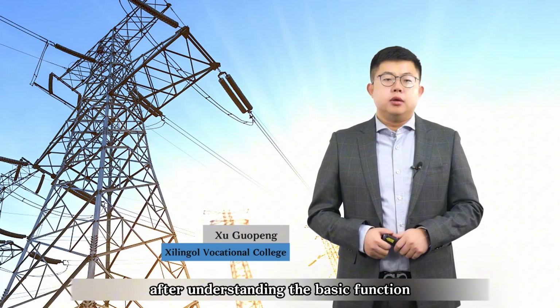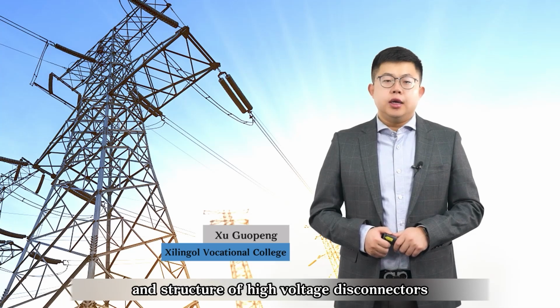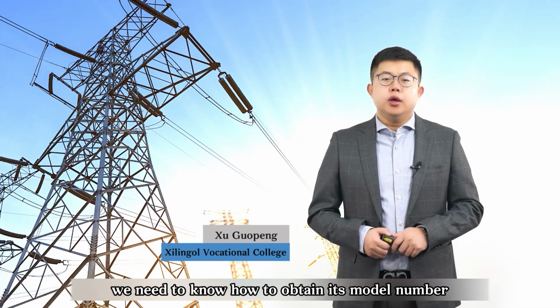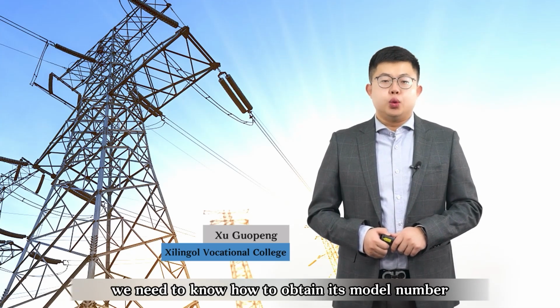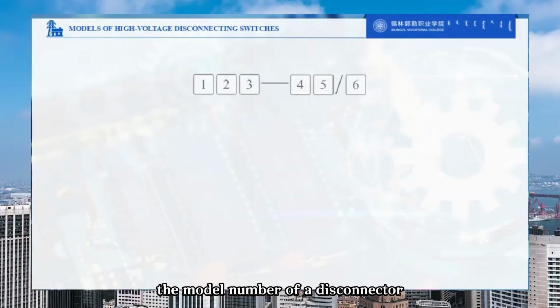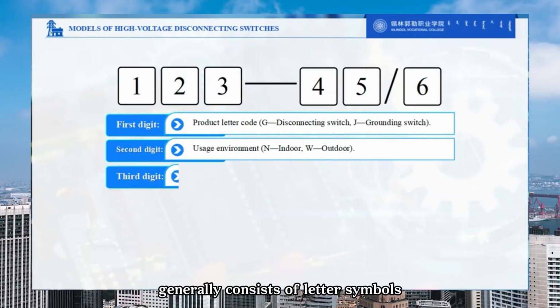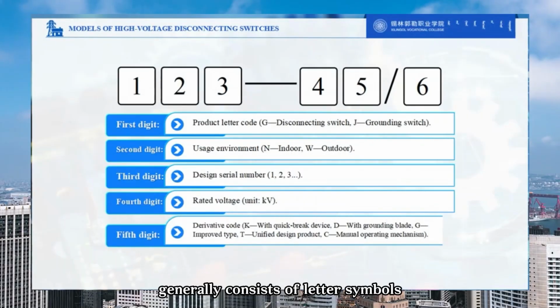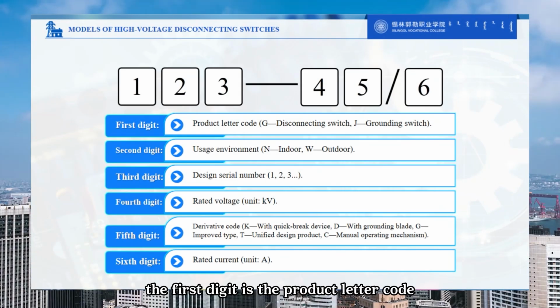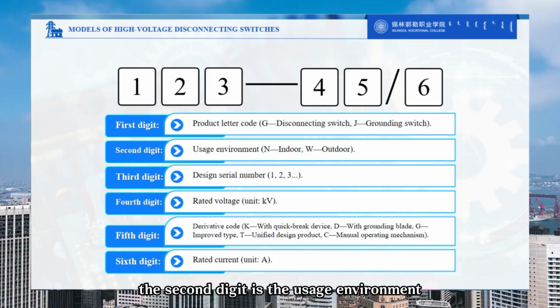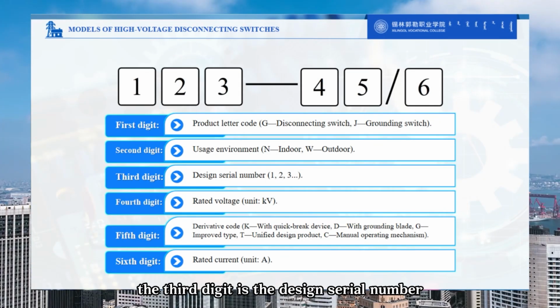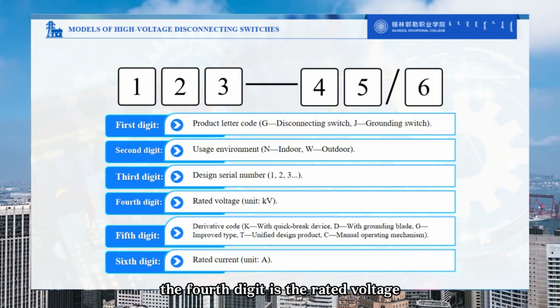After understanding the basic function and structure of high-voltage disconnectors, we need to know how to obtain its model number from the nameplate. The model number of a disconnector generally consists of letter symbols and number symbols. The first digit is the product letter code. The second digit is the usage environment. The third digit is the design serial number. The fourth digit is the rated voltage.